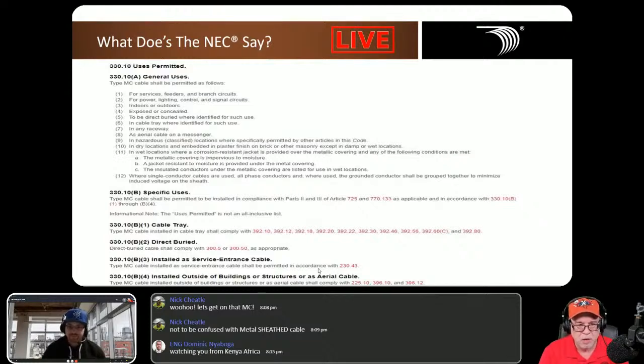Another example is 330.10b1. It says cable tray. So here's what it says. It says type MC cable installed in cable trays shall comply with 392.10, .12, .18, .20, .30, .46, .56, .60C and .80 of 392. Obviously, 392 is for cable tray. Now, the reason we have this, Jay, is because if I put MC cable in a cable tray, there's other things I have to be aware of. Spacing, layering, ampacities, clearances, all these type of things if I'm going to install this inside of a cable tray. And if you go look at 392, it's going to tell you that MC cable can be in a cable tray. So this is just kind of correlation to say, okay, it's perfectly fine for MC cable to be installed in cable trays as long as you meet the rules in 392 as referenced here at 330.10b1.